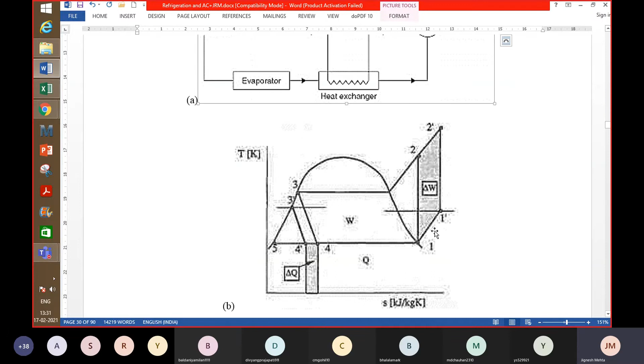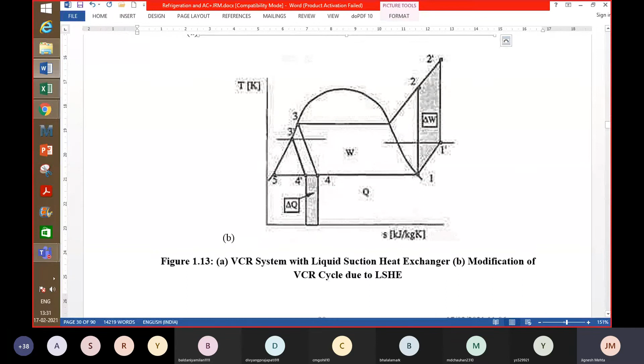Okay, but then even if there is sometimes a little drop in COP, which is probably not very significant, the quality of the vapor that you get at the outlet is better, and that's also good for better functioning of the system. So you may sacrifice the COP a little bit, and you may still go for subcooling, which helps you get more liquid in the evaporator as well as less flashing in your expansion device. So this is about the liquid suction heat exchanger. So that is another way one can achieve subcooling.